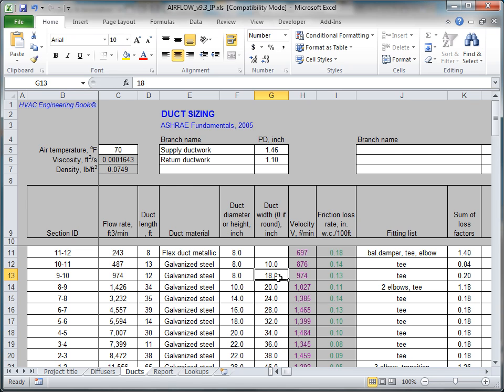Lastly, we need to calculate the impact of fittings and dampers on the total pressure loss in the duct work. To do this, obtain the corresponding fitting loss coefficients for each of these elements. For learning purposes, you may use loss coefficient tables provided in our A-Z HVAC design course.